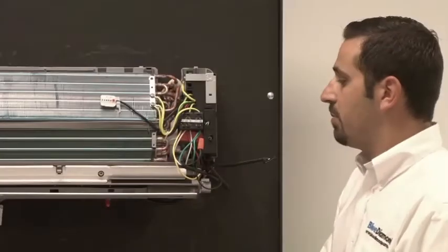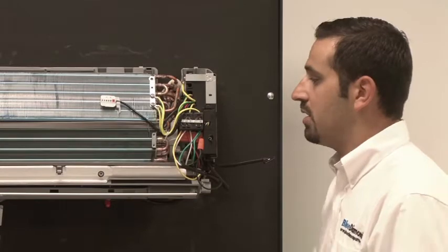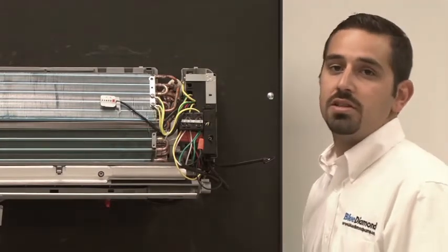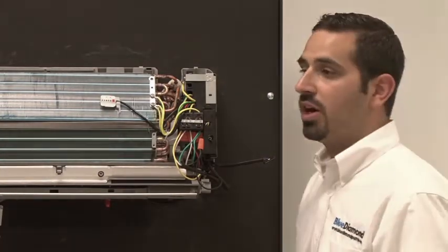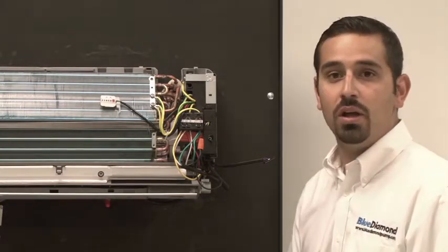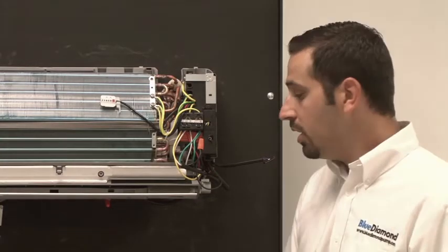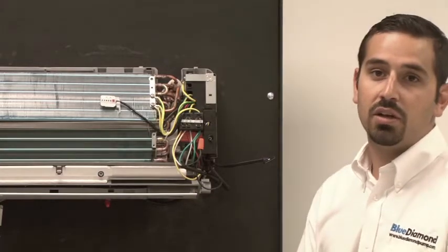All right now that the wiring is complete we just want to make sure that everyone understands that we are not running L2 or S through the pump. The only thing we will break with the Blue Diamond pumps is your L1. L1 will run through the pump, use our normally closed contact to bring the voltage back to your air handler.